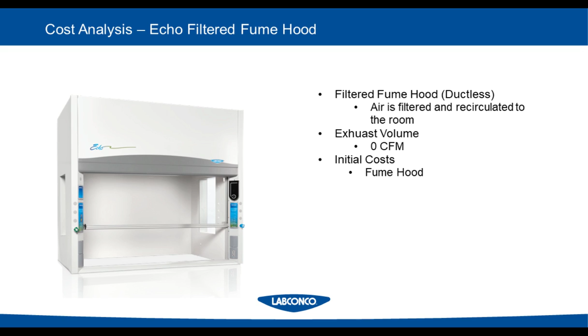I wanted to look at a final cost analysis with all three of these put in one slide. You can see that the total capital equipment cost for the Echo filtered fume hood is actually less than that of the variable air volume fume hood at approximately $38,520. Where this hood really excels is in that makeup air portion. It has $0 per year since you are recirculating air, so that $8 per CFM does not apply here. It does have a little bit higher maintenance costs per year because you do have the filters associated with the fume hood, but that $2,093 of total operating and maintenance costs per year more than makes up for that.